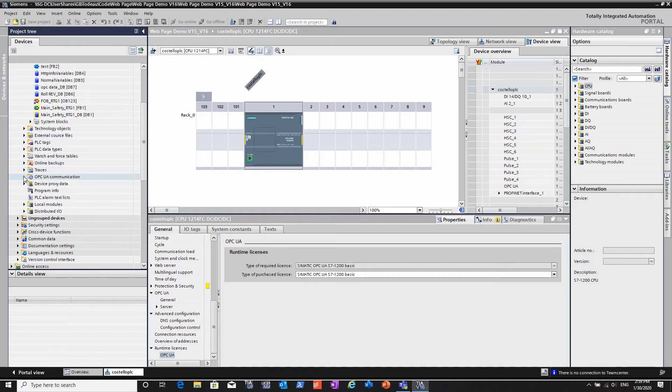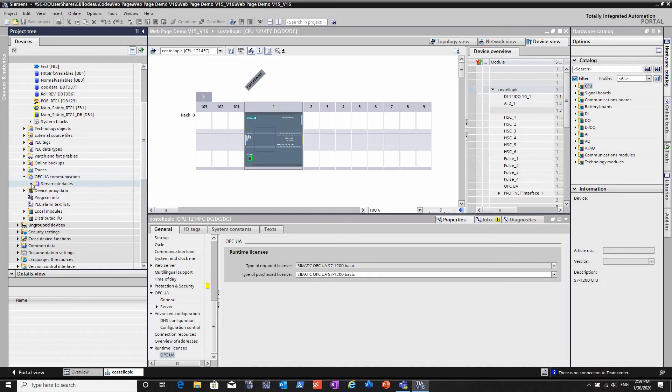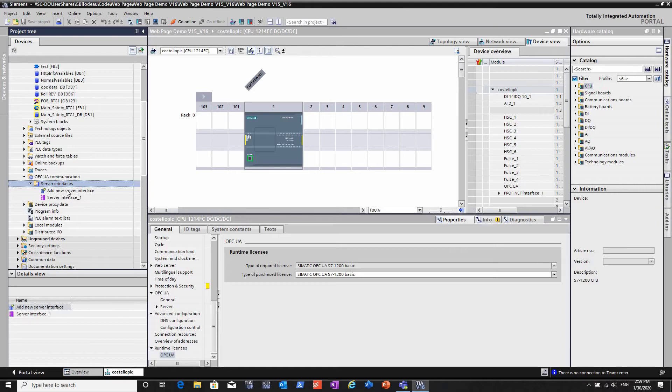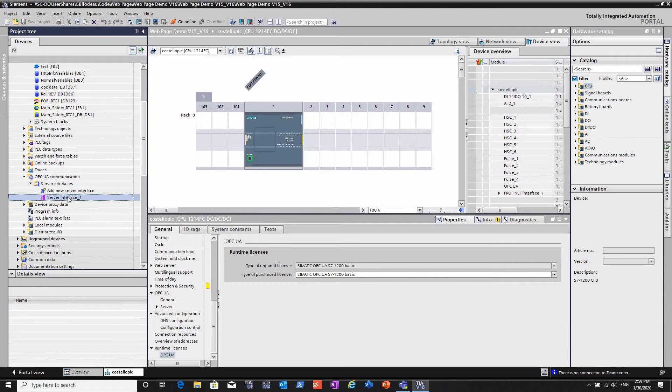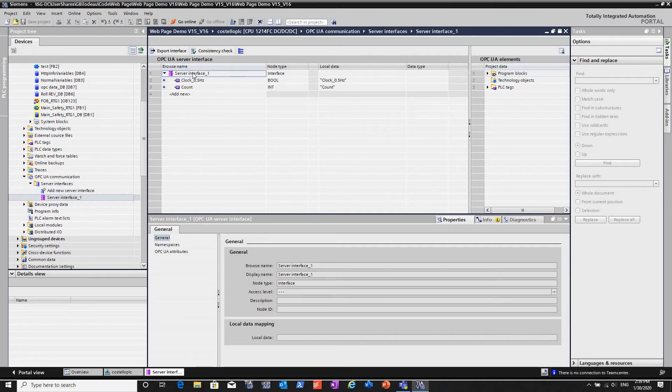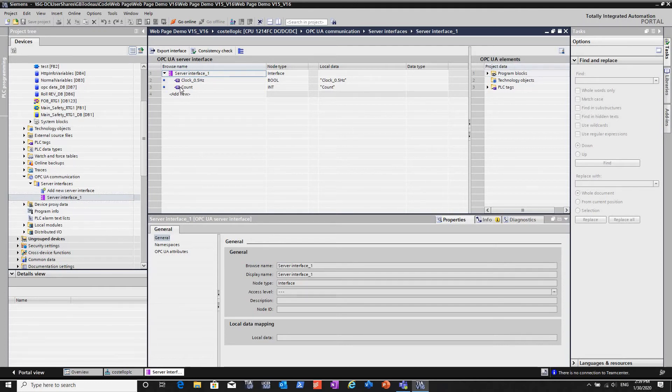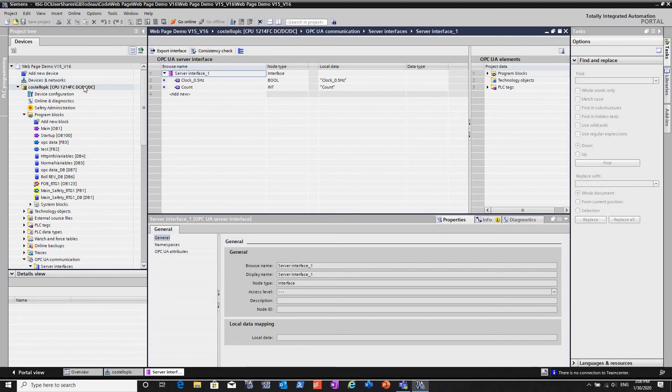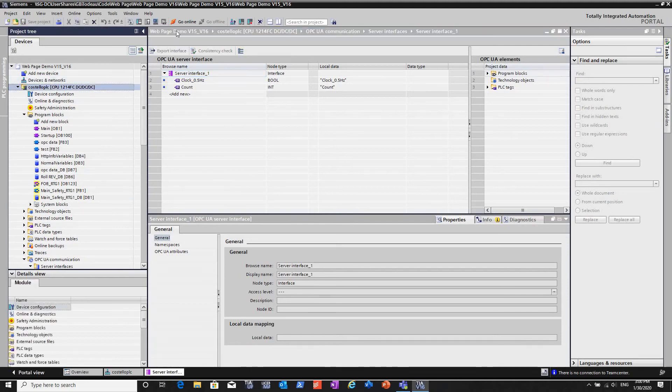Now that I've enabled the OPC UA server, I have to select what's actually going to be visible to the OPC client. I've got the server, then I've inserted just two variables. Those two variables will now be visible from OPC clients and browsers. If it's not in here, it's not visible and cannot be read.